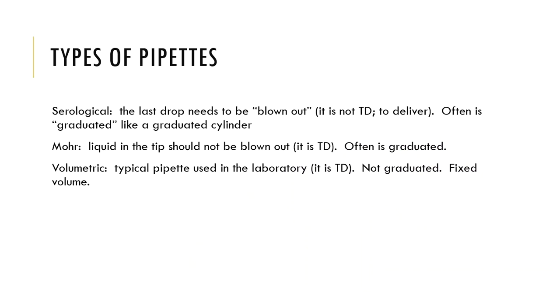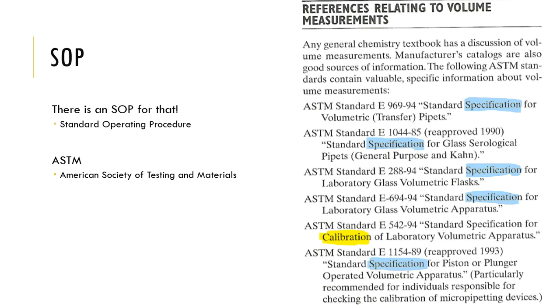Other types of pipettes include serological pipettes, which are TC (to contain). Volumetric pipettes and Mohr pipettes are TDs. There is a standard method from the American Society of Testing and Materials (ASTM) that labs must follow to verify volumetric pipettes work properly. Relevant standards include E969 for volumetric pipettes, E1044 for glass serological pipettes, E288 for lab glass volumetric flasks, and E694 for lab glass volumetric apparatus.